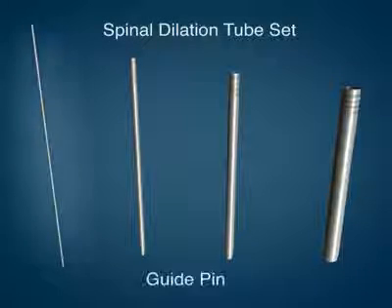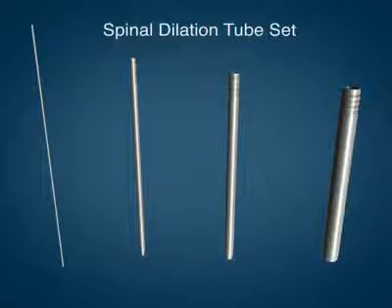For the minimally invasive procedure, an additional set of instruments are needed called the spinal dilation tube set, which contains a guide pin and three dilation tubes labeled tube one, two, and three.